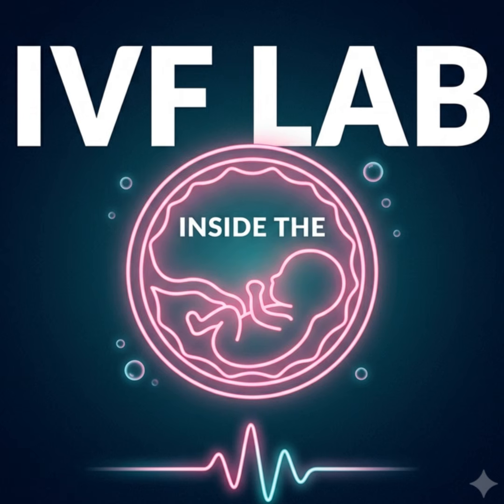As I mentioned, the machinery rarely fails loudly. It drifts silently out of specification. And when the physical environment drifts, that mechanical error translates instantly into physical and thermodynamic stress on the cellular biology. So the cells feel it first. The embryologist might notice that they are having a slightly harder time getting the injection needle to snap cleanly through the membrane, perhaps because the approach angle has drifted by 2 degrees, causing more geometric distortion.